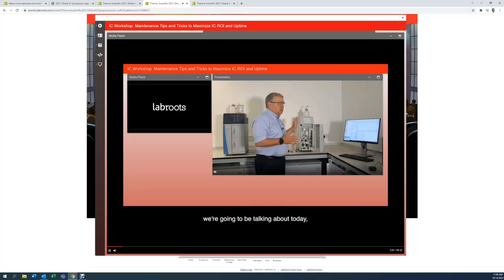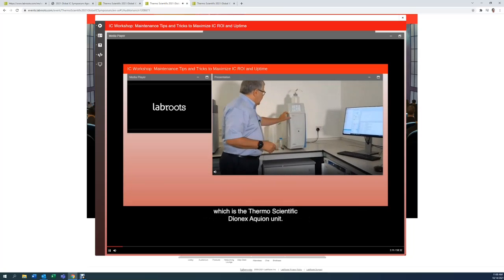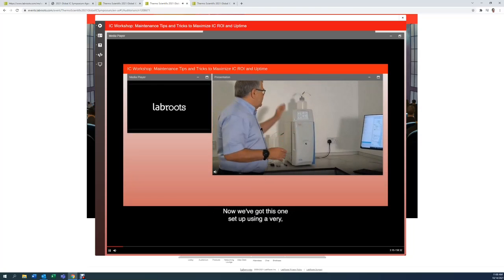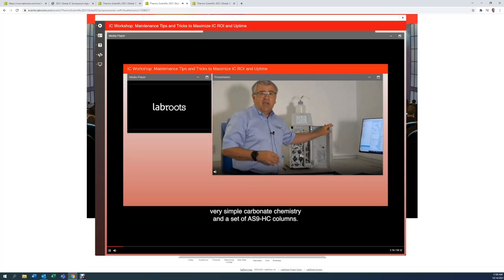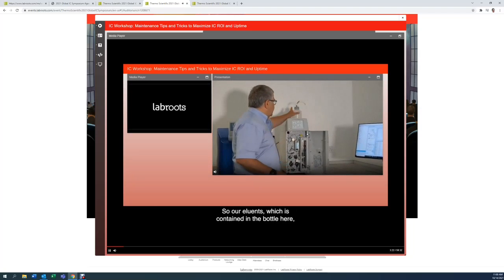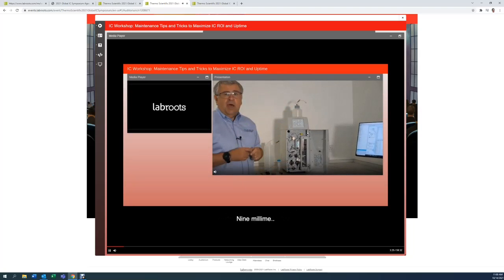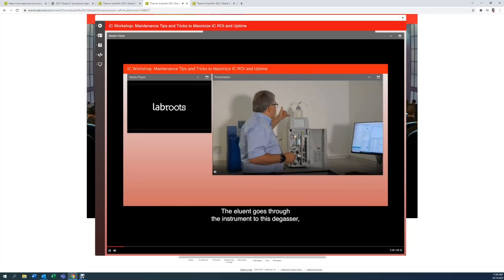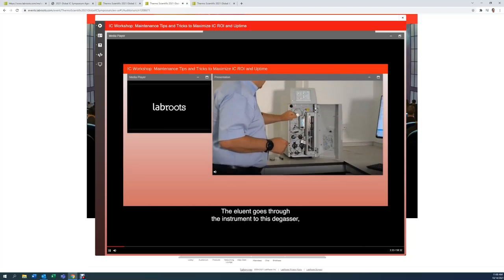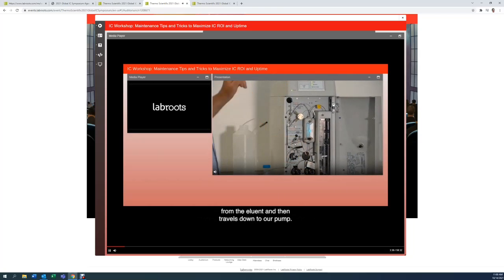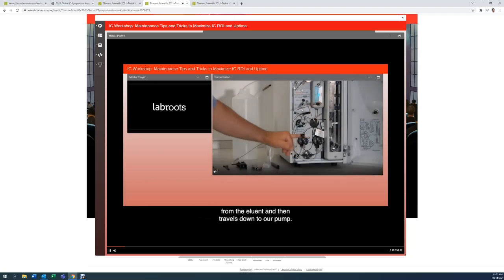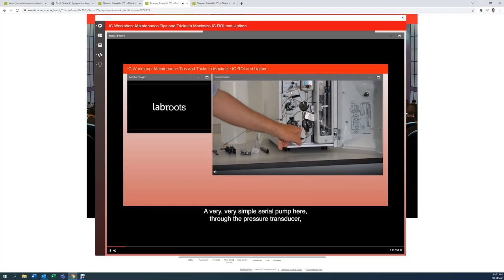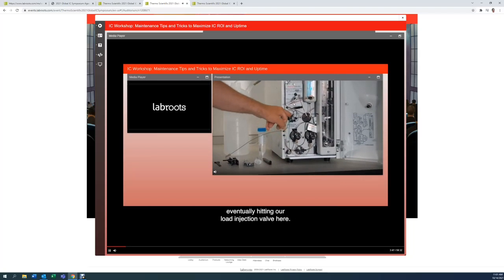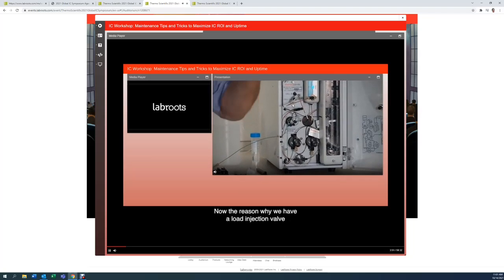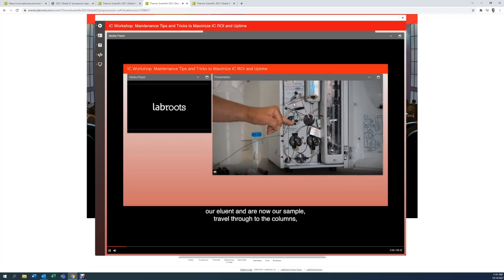I'd like to introduce the instrument that we're going to be talking about today, which is the Thermo Scientific Dionex Aquion unit. We've got this one set up using very simple carbonate chemistry and a set of AS9-HC columns. So our eluent, which is contained in the bottle here, is a very simple 9 millimolar sodium carbonate. The eluent goes through the instrument to this degasser, which just removes any excess gas from the eluent, and then travels down to our pump, a very simple serial pump here, through the pressure transducer, eventually hitting our load injection valve here. The reason we have a load injection valve is to introduce sample to the eluent stream. Our eluent and our sample travel through to the columns.